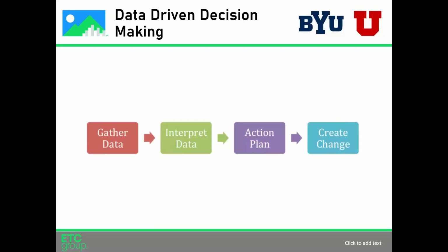It's tied into our HVAC, and we create a list, and I can send my electrician and a technician to those zones, those individual spaces, and say, this space is not following schedule. Please check the sensor and the associated relays. And we find all kinds of things that were done wrong or have just failed that we would have never known.